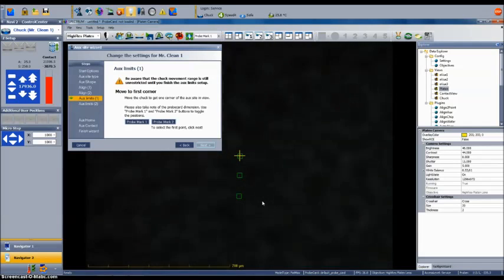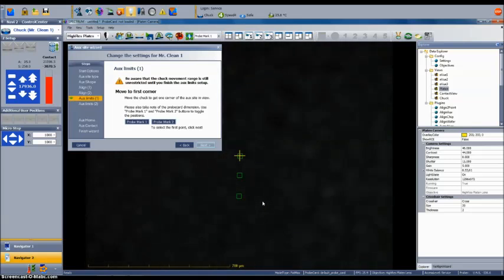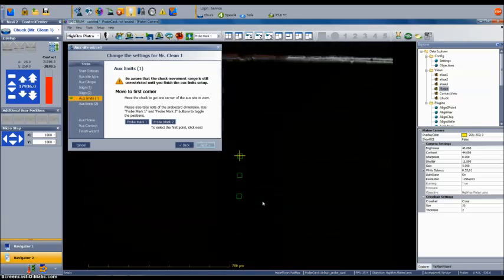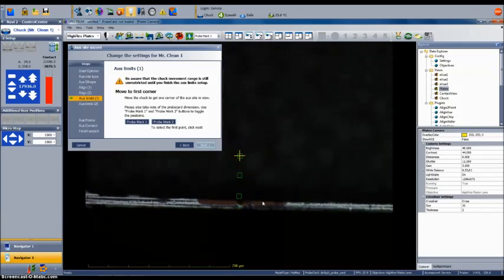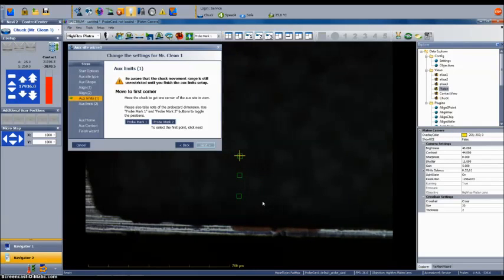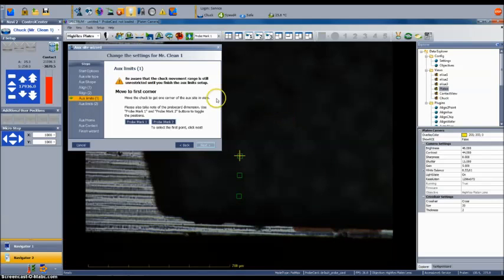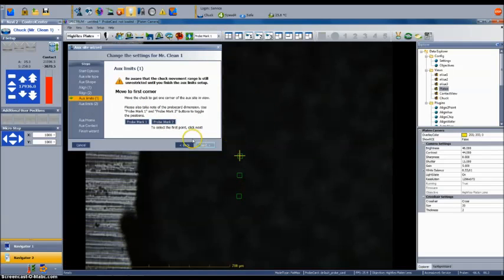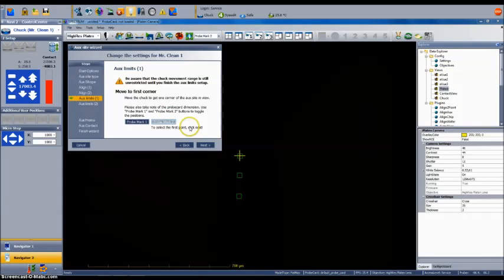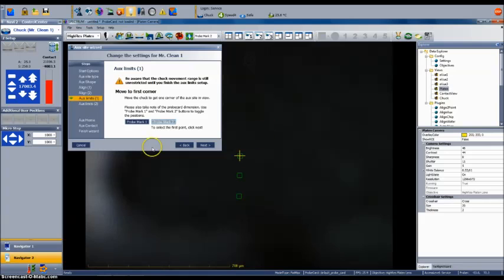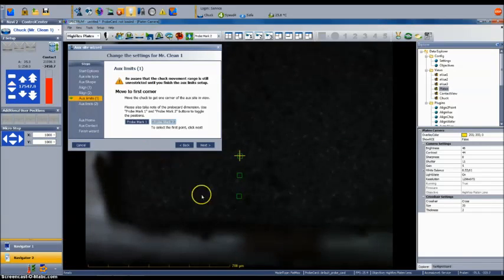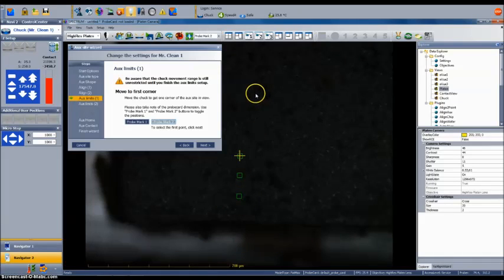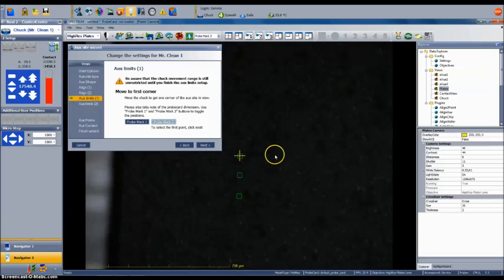For a vertically oriented probe array, you want to make sure that the lower tips do not fall off the bottom edge of the cleaning pad surface. When setting up the probe array in a different wizard, I set probe mark position 1 to be at the top of the array and probe mark position 2 to be at the bottom of the array. Since we are setting the lower fence boundary using the aux limit 1 position, select the probe mark 2 button to reference the crosshairs using the bottom of the card. Also make sure to take into account any registration error you may have seen when you install the cleaning pad. You want to add in a keep out region of 1 to 2 millimeters along each pad edge. Here I select probe mark 2 and then refocus on the pad surface, and then move the crosshair into position to set my keep out zone.